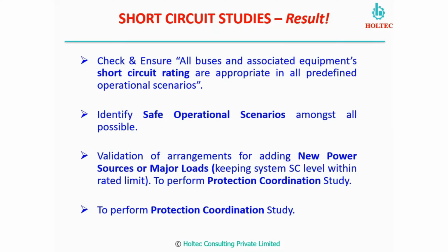What are the results which we can obtain from these short circuit studies? The first thing is that we can validate or decide the rating of all buses and the associated equipment, so that your system will be safe. The next one is the safe operational scenario amongst all possible options.